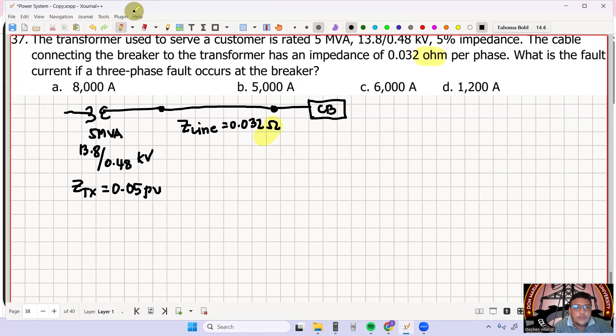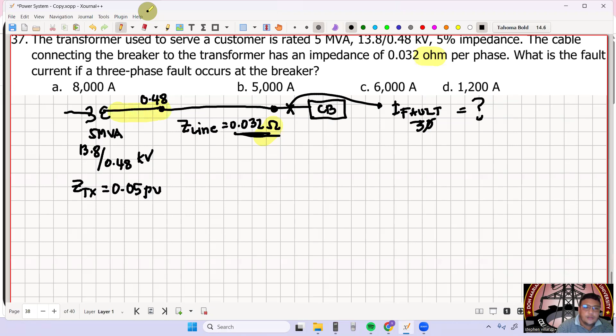So when there is a three-phase fault, what is I fault? Again, in solving for fault current, we first need to convert everything to per unit. So the ohmic value of Z line, we convert to per unit. Take note of the voltage to use: since Z line is connected at the secondary of the transformer, the voltage is 0.48 kilovolts.